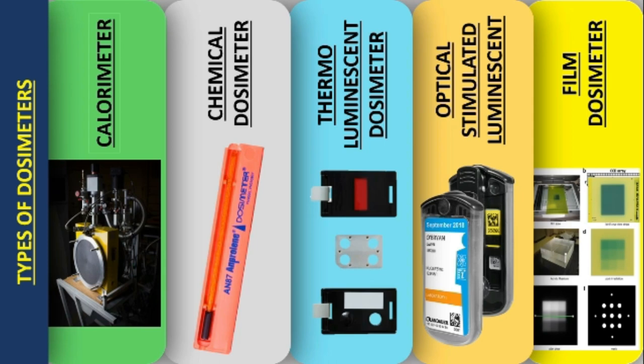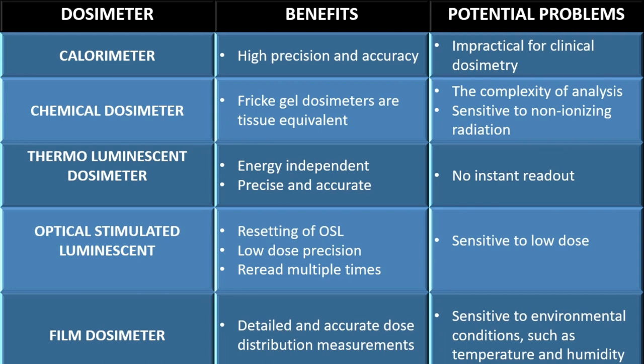All of these dosimeters have some positive and negative points. The calorimeter is precise and accurate for measuring absorbed dose, but it is not suitable for routine use in a clinical setting. The material in a chemical dosimeter is tissue equivalent, but it is also sensitive to non-ionizing radiation. Both the calorimeter and chemical dosimeter are time-consuming and require sophisticated equipment.